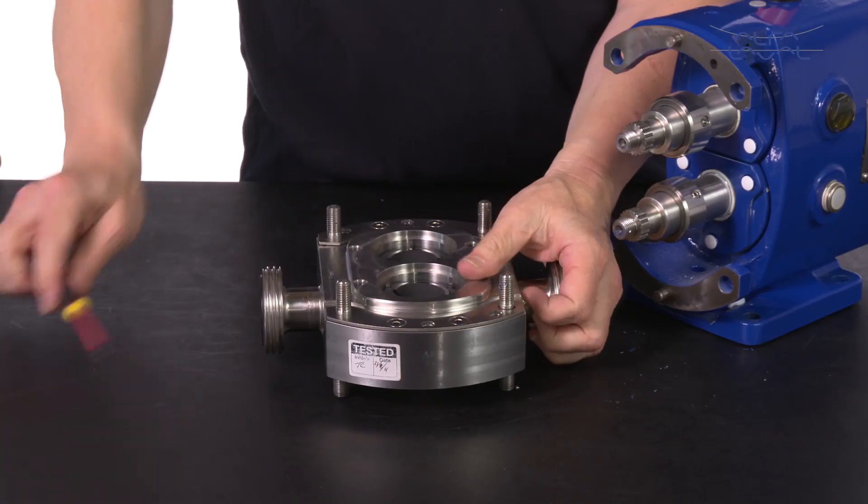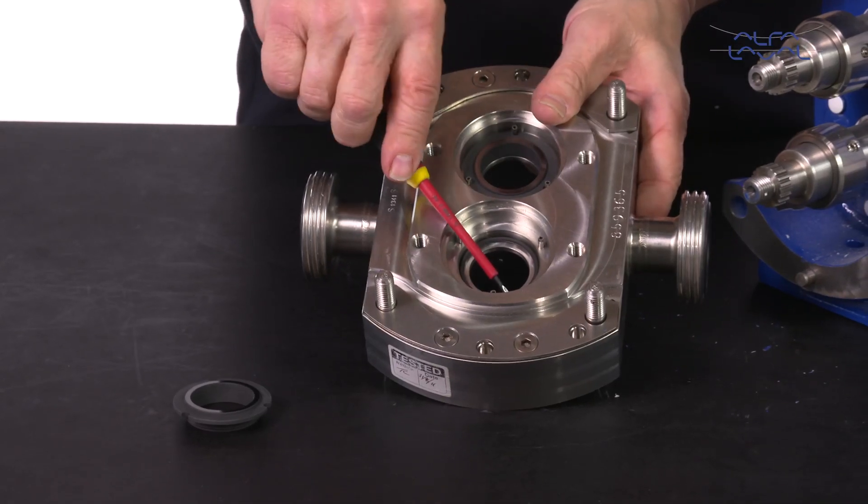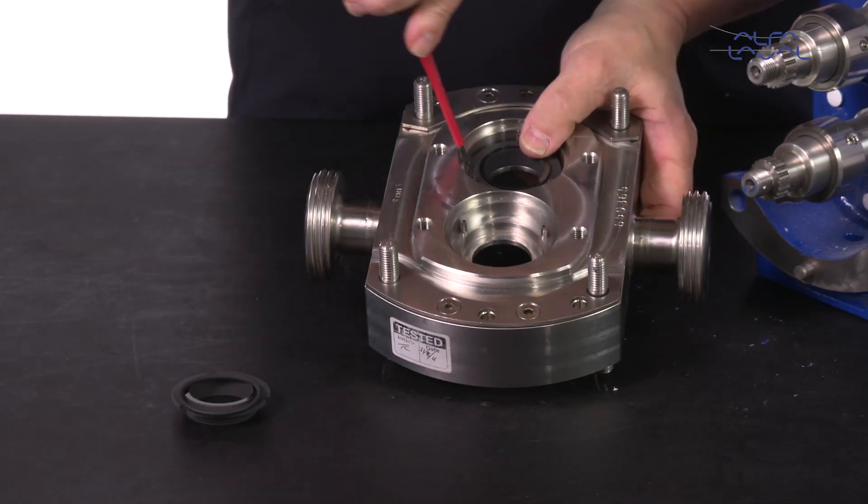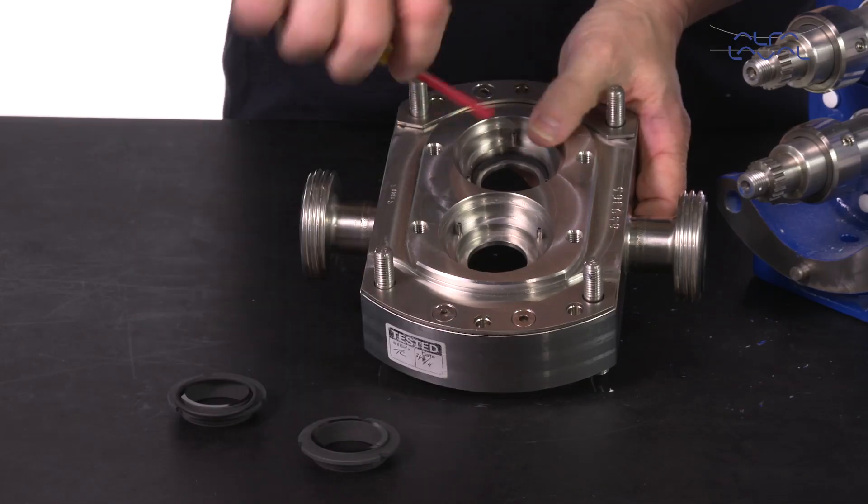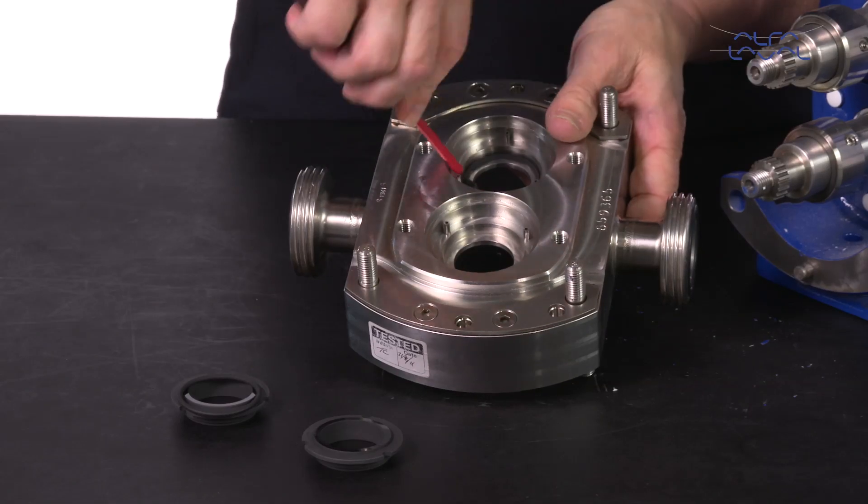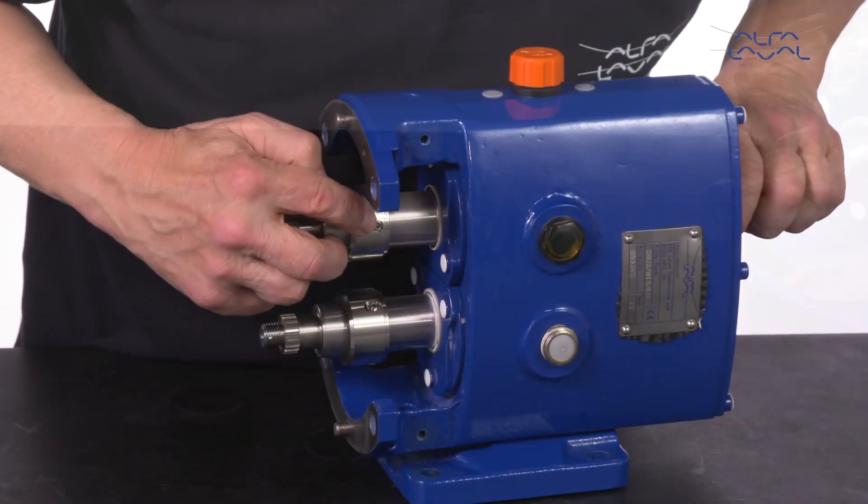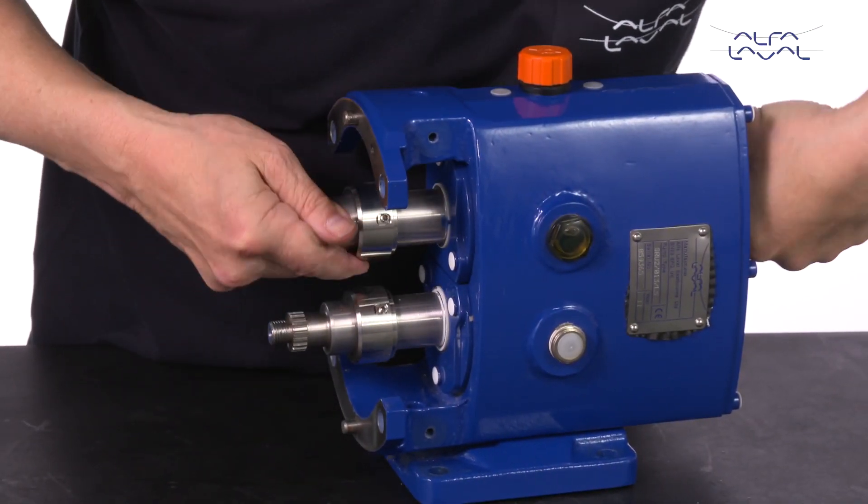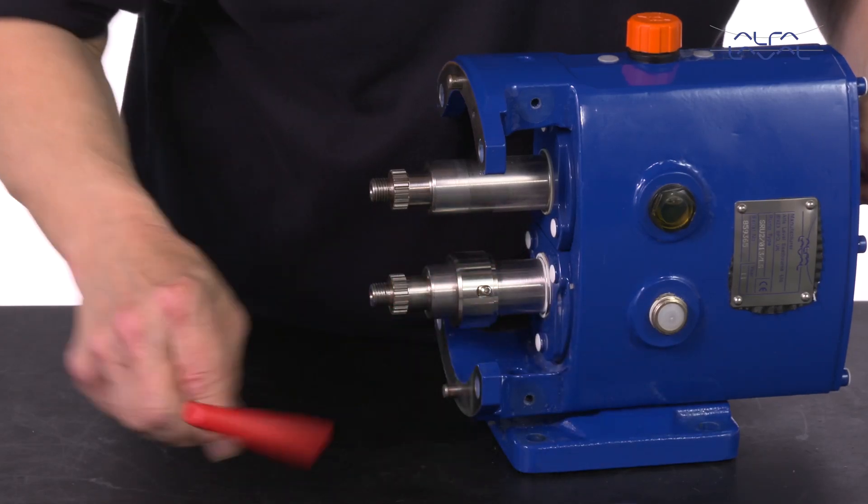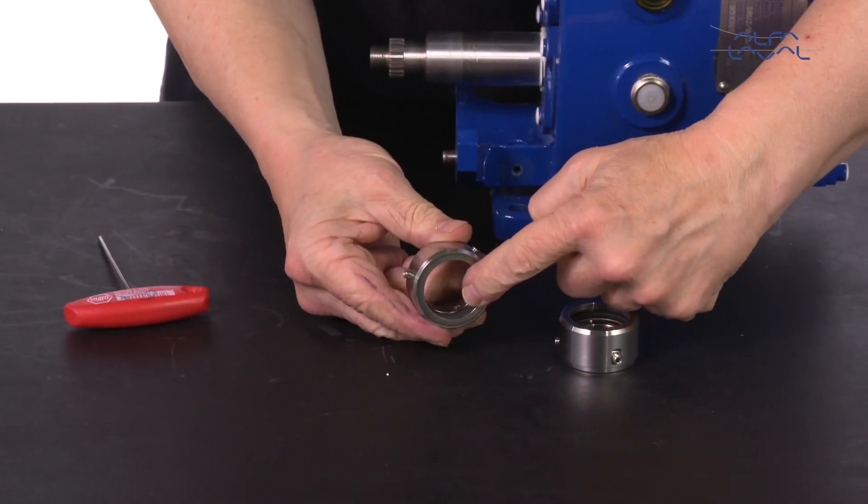Now extract the stationary seal rings and O-rings from the rotor case. Unscrew the grub screw on the rotating shaft seal and remove it from the shaft. Then remove the internal O-ring.